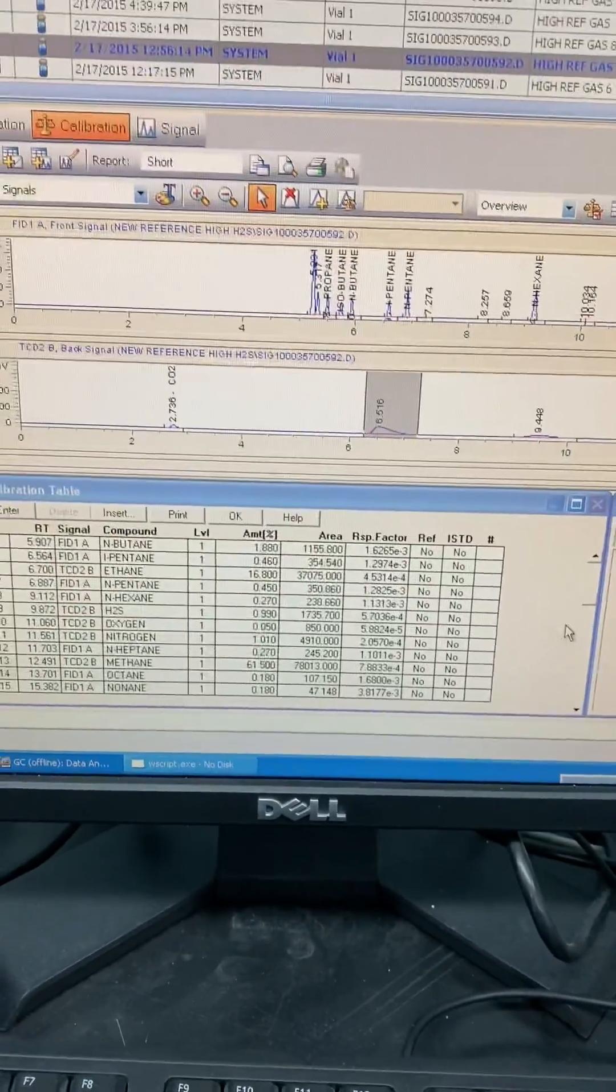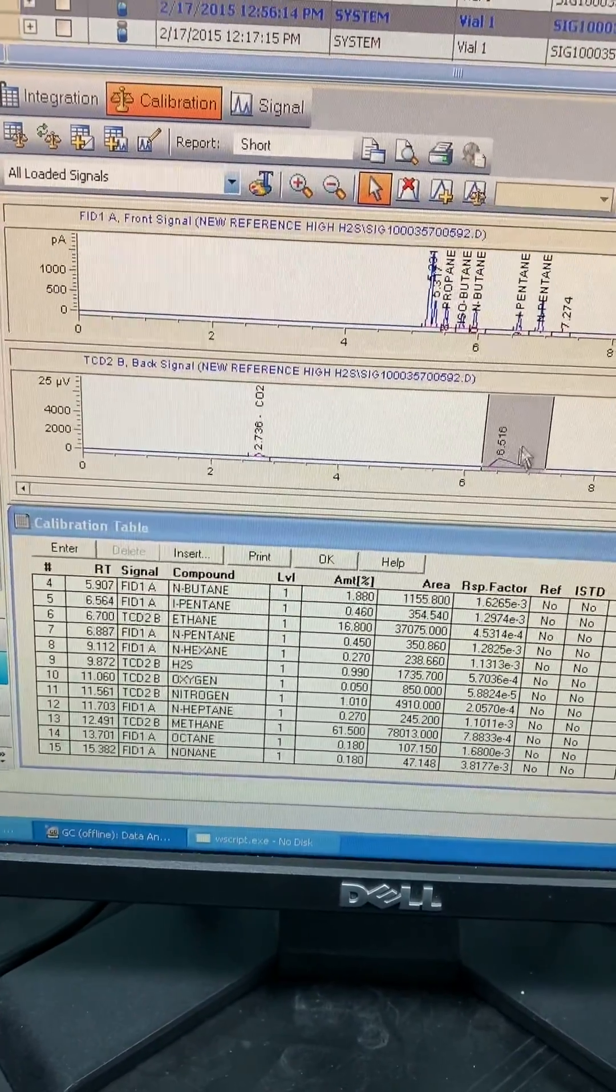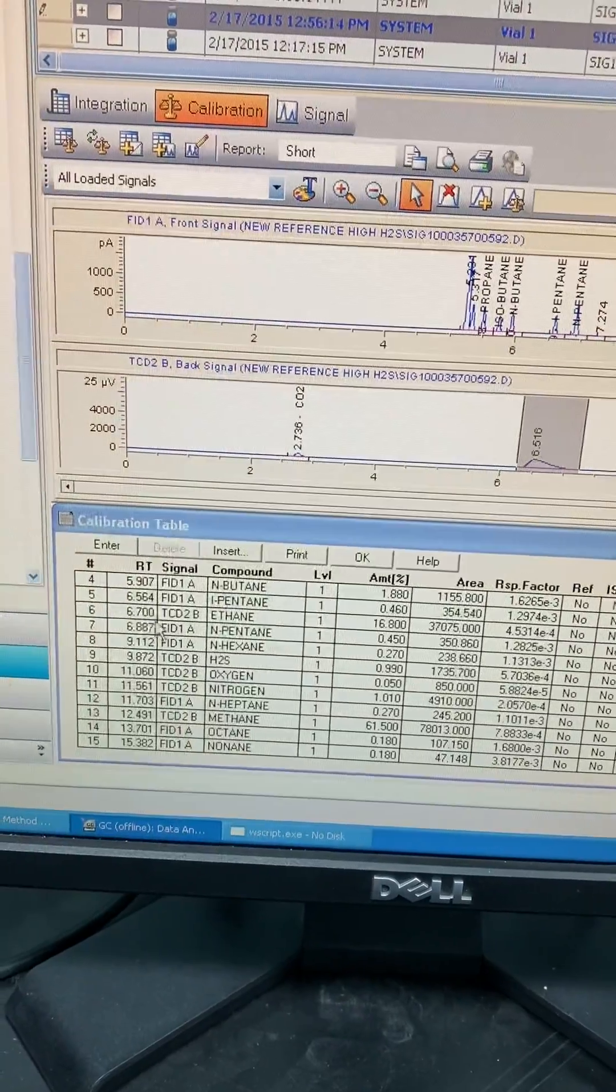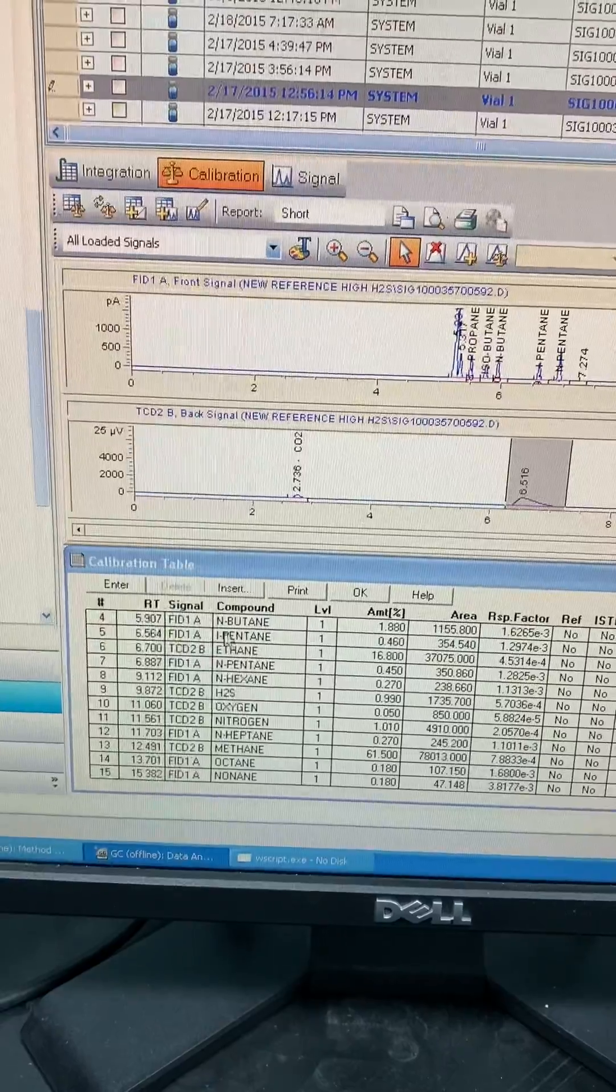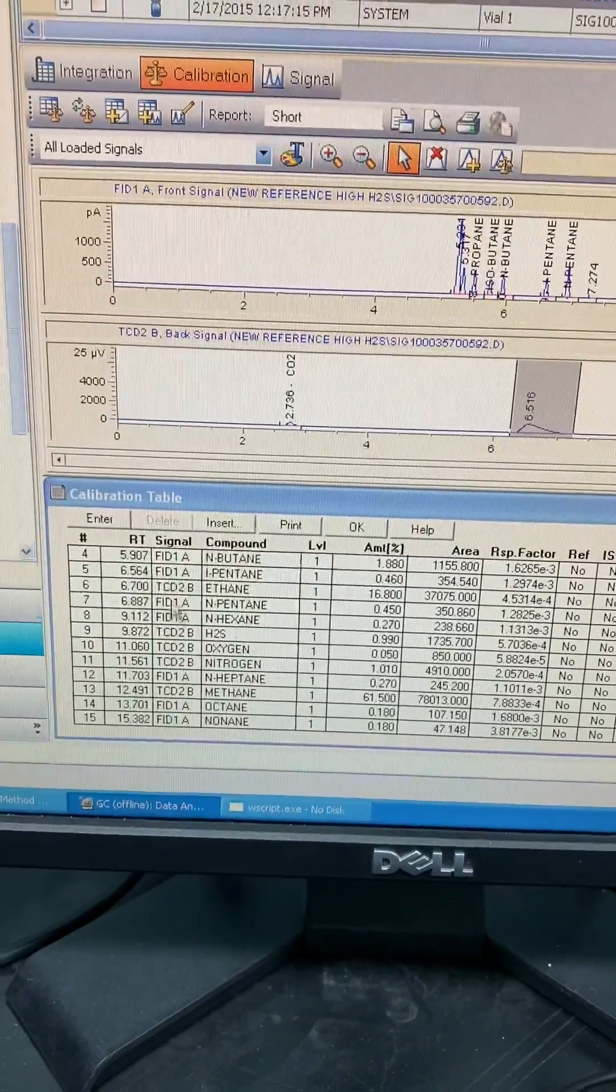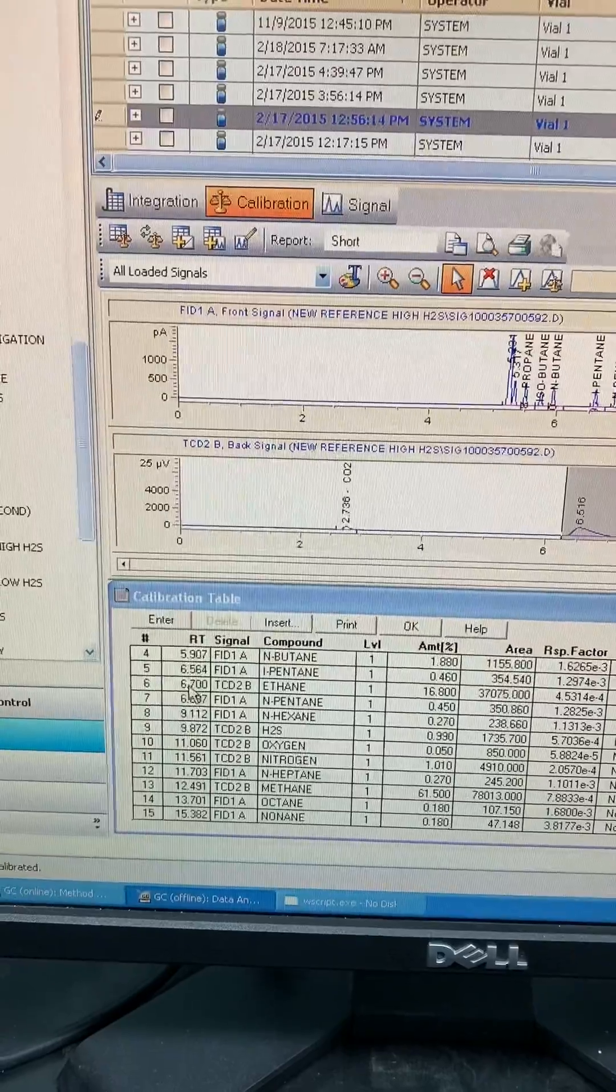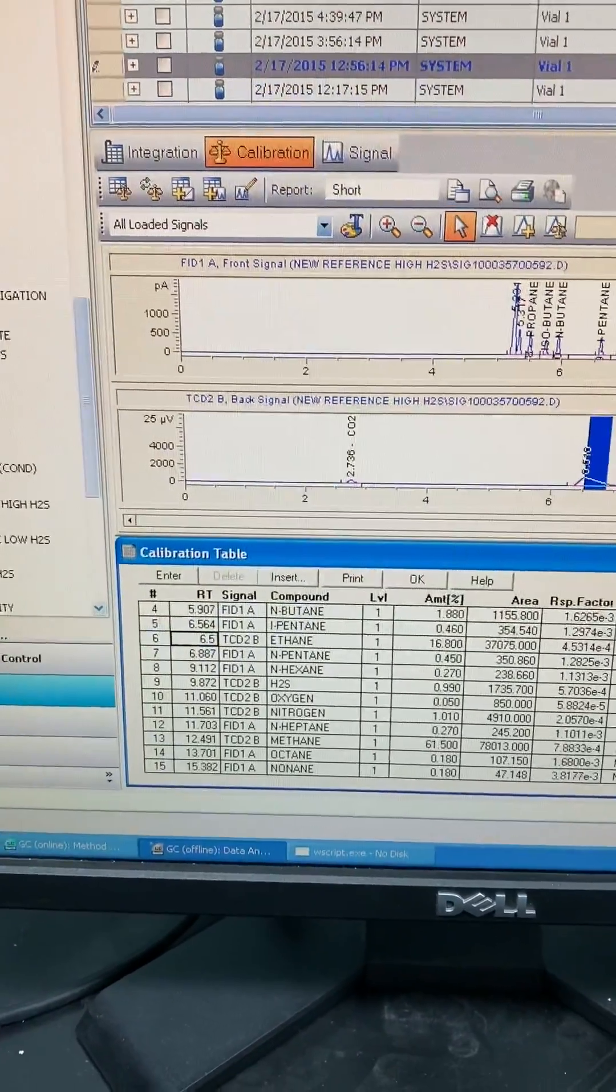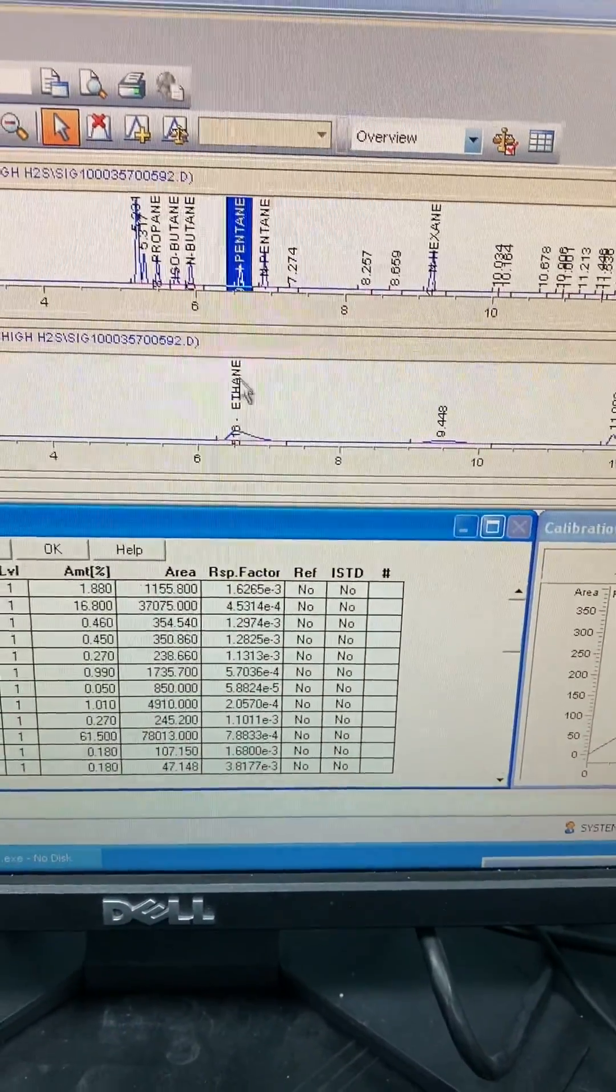How to know? You will go to the table and see, near to this 6.5, what I have as component. I have normal butane and ethane. But this chromatogram related to TCD detector. That means I will see the signal. TCD, you will see ethane. You can change the retention time from 6.7 to 6.5 and press enter. Now, the peak will be identified.